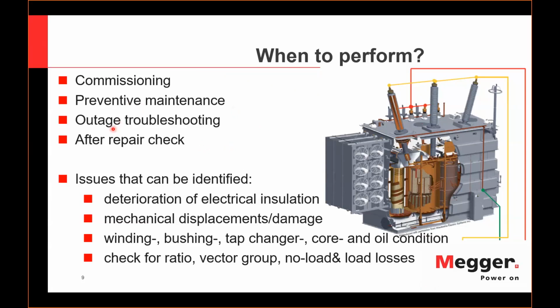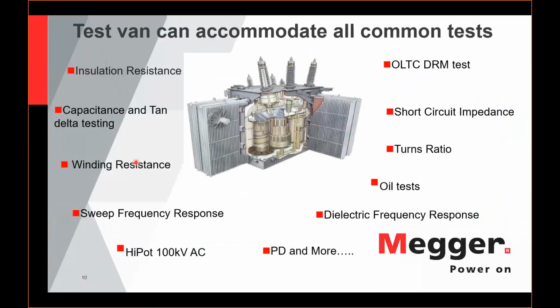In case an outage still takes place, you need an electric toolbox to localize the problem, to troubleshoot and to figure out what component is affected and how to fix it. Whether you scheduled an outage or experienced an outage, and even conducted a repair on site, or even needed to send the unit back to the factory, you must make an after-repair check to see if all the wiring has been done properly before you energize the equipment again.